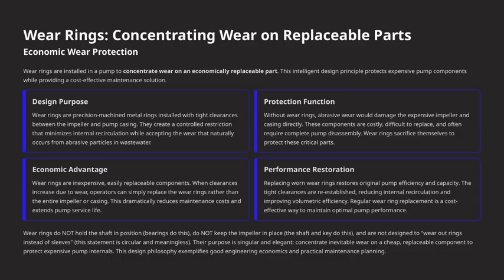Now, let's look at wear rings and how they help concentrate wear on parts that are replaceable and cost-effective to maintain. Wear rings are installed in the pump to trap wear on a part that can be easily replaced, which protects the more expensive components. This design is quite intelligent because it allows us to save money and time on maintenance. The purpose of wear rings is very precise.